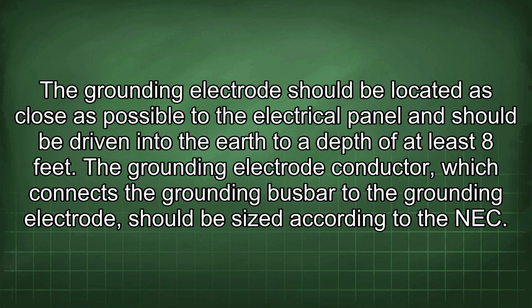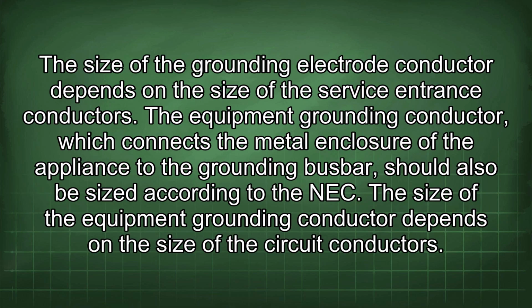The grounding electrode should be located as close as possible to the electrical panel and should be driven into the earth to a depth of at least 8 feet. The grounding electrode conductor, which connects the grounding busbar to the grounding electrode, should be sized according to the NEC. The size of the grounding electrode conductor depends on the size of the service entrance conductors.